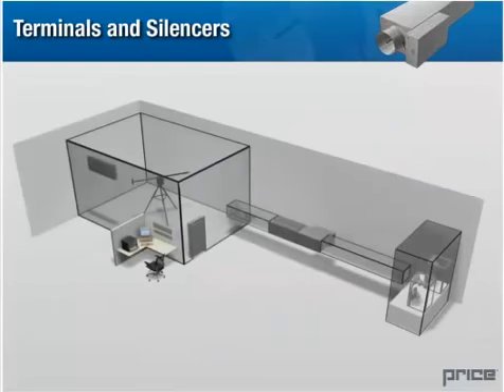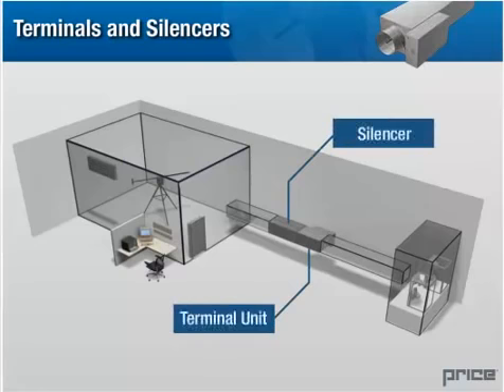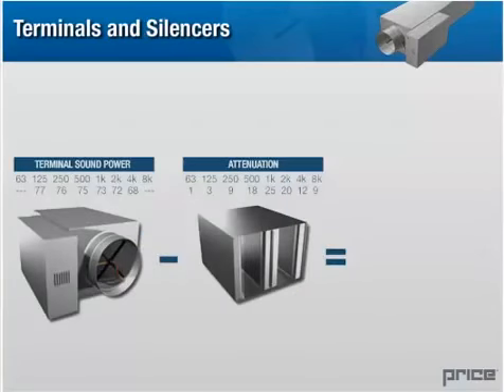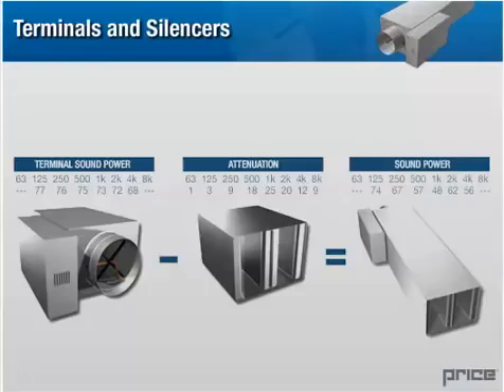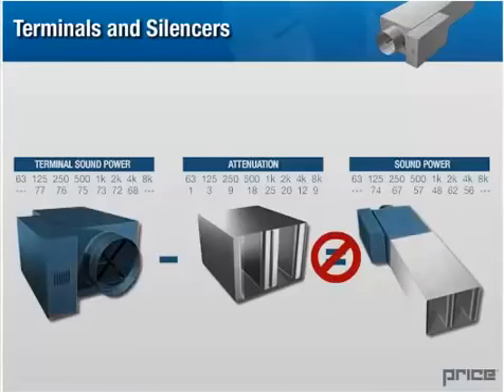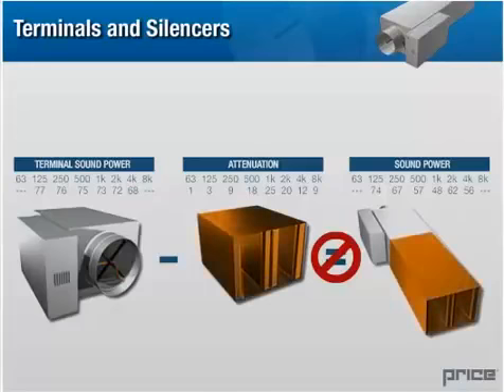An alternate method of attaining NC ratings of silencers is to actually set up the terminal unit complete with silencer in an ARI certified reverberation chamber and measure the results. Theoretically, when the calculated and tested values are compared with each other, they should be equal. In actuality, the results can be astoundingly different. More often than not, the performance of a standard terminal unit close coupled to an industry standard silencer does not perform anywhere near what the calculations predicted.